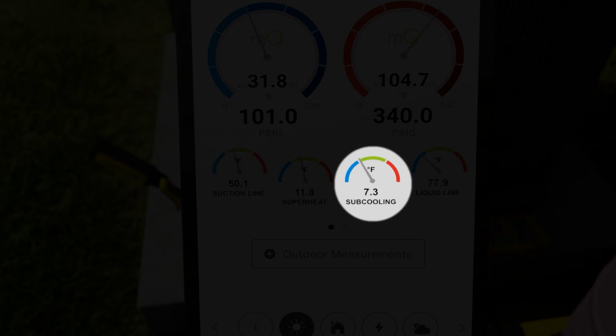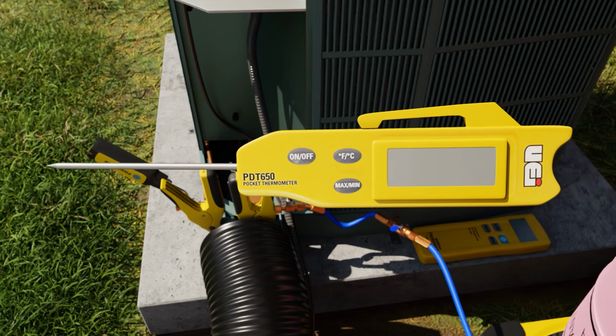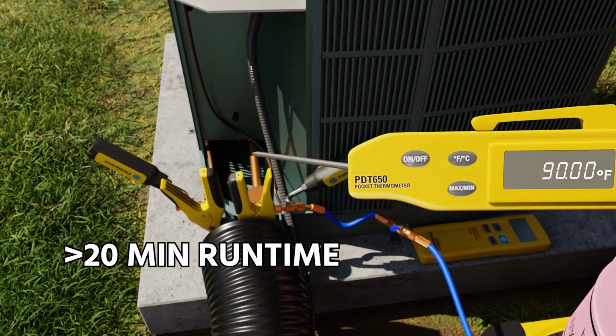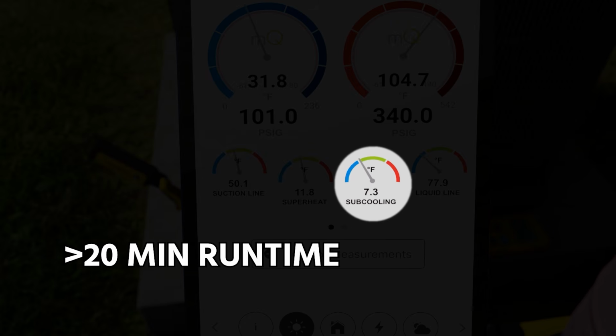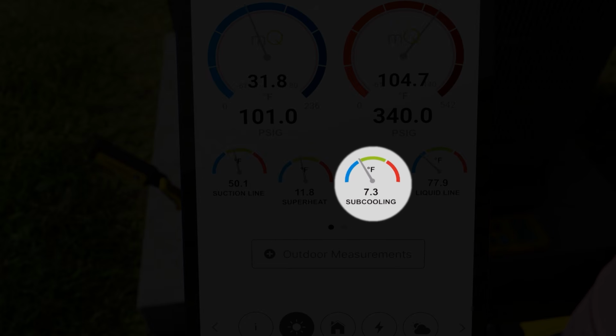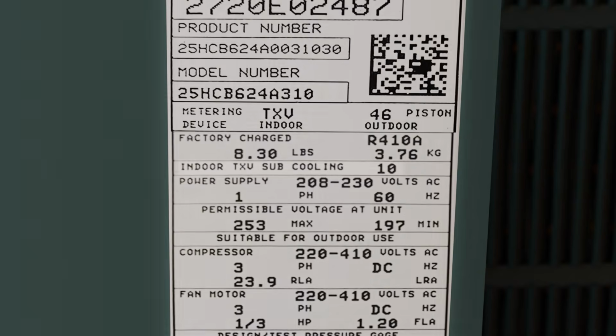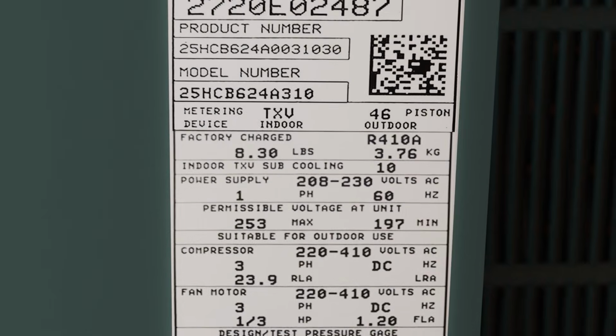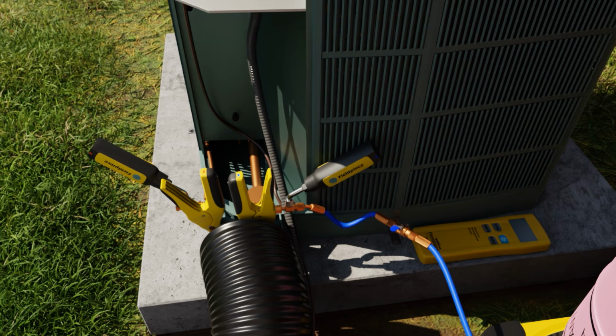Now, monitor your system pressures and specifically watch your subcooling. You'll only want to make adjustments after at least 20 minutes of runtime, but hopefully even more than that. Here we're showing that we're measuring a low subcooling using the MeasureQuick app. We're showing a 7.3 subcooling with a listed subcooling on the data plate of 10. Now that's not really realistic here because we know we only have a 15-foot line set, but we're showing adding charge for the sake of the video.